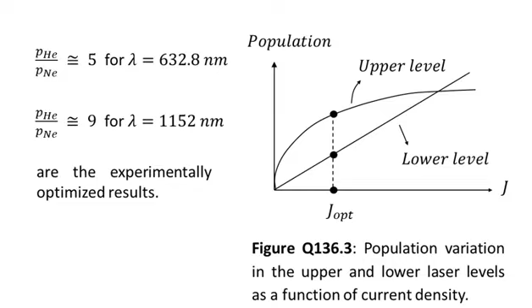Helium neon power supply designs use optimum current values and thus optimum current density, marked as J opt, as shown in figure number 3. PD is the pressure times the diameter of the capillary tube. PD should vary in the range from 3.6 to 4, where pressure is measured in torr, whereas the diameter D is measured in millimeter, where P is the total pressure and the capital D is the capillary diameter. This is an experimentally optimized relationship. So PD should vary in this range of 3.6 to 4. This is an experimentally optimized parameter.